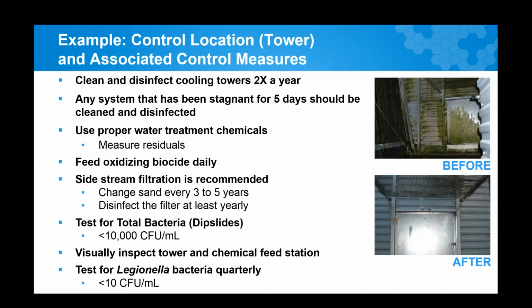You'll feed your oxidizing biocide daily. You'll have a program for your side stream filtration, test for total bacteria, visually inspect the tower and chemical feed station, and record that this is happening. Documentation is very important here.